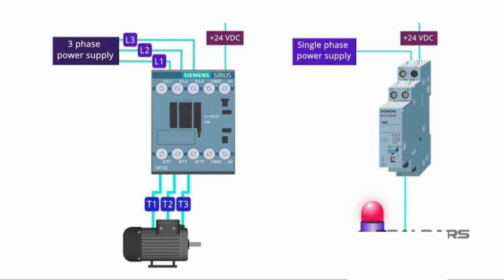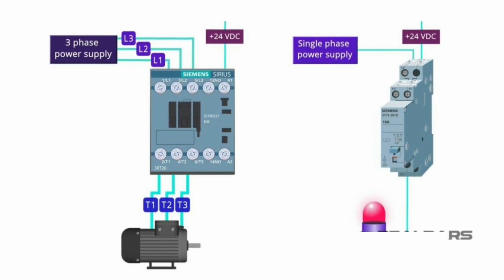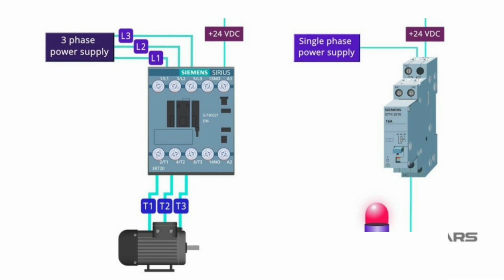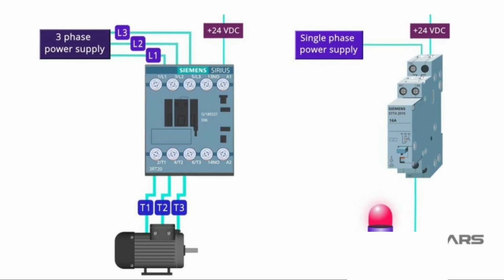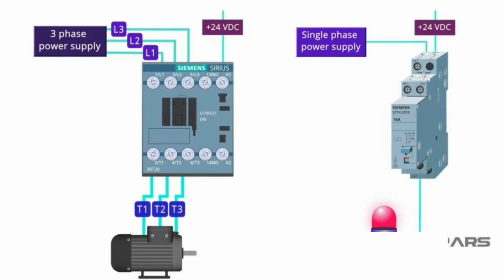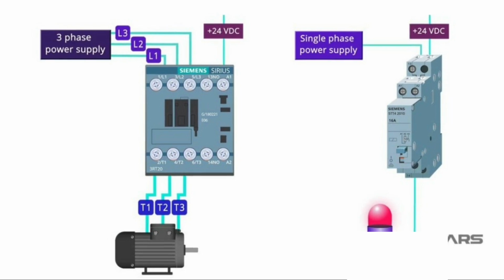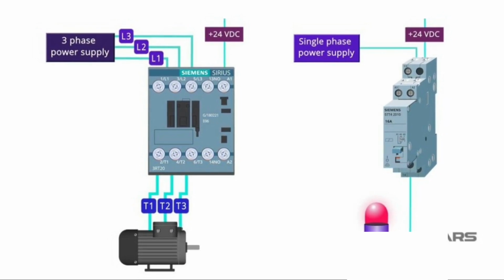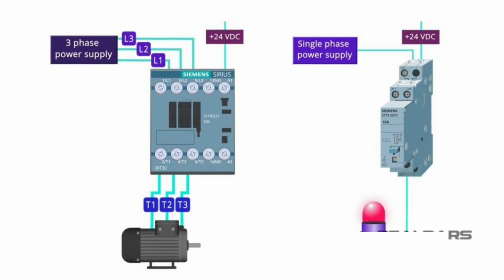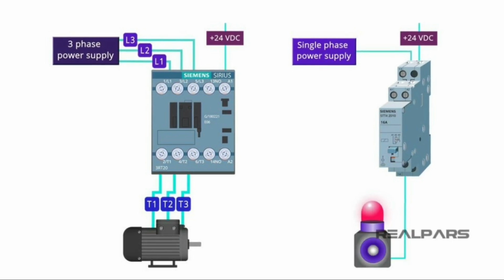But here is the difference. A relay is usually used for smaller devices with lower current and voltage rates. A contactor, however, is used for bigger devices with higher current and voltage rates. So, relays are used to turn on and off small devices and contactors are used for turning on and off bigger devices. Very simple.